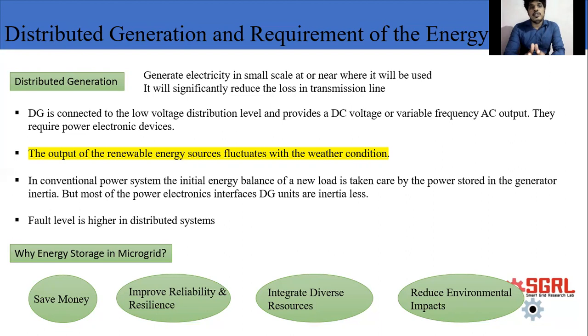That is why we use an energy storage system, basically a battery energy storage system, in order to withstand that demand increase, since existing power electronic interfaces are inertialess and don't have much reserve capacity. The fourth point is that the fault level is much higher in distributed systems than in conventional systems.